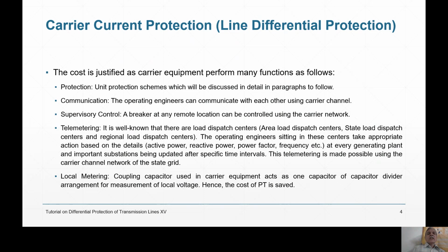And obviously local metering, because you have got a coupling capacitor. So in series with the coupling capacitor, if you connect a low voltage capacitor, you can get a low voltage of 110 volts, and you do not require a separate PT. So the cost of the PT is saved. So because of so many advantages, because of so many functions that the carrier current equipment performs, they are justified. That one should know.